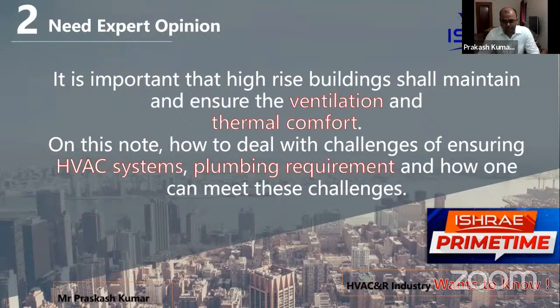Hi everyone. I think this is a wonderful question because piping and ducting are normally one of the most crucial parts of any air conditioning system. In high-rise buildings it becomes paramount because generally these buildings are glass covered, so there's nothing we can do outside the glass cover as it would damage the elevation. Starting with chilled water piping, we generally provide a dedicated shaft from the chilled water plant, located at the ground floor or basement, to each AHU room on each floor. The chilled water shaft should be adjacent to the AHU room, but after erection of the pipe, the common wall between the AHU and shaft should be completely sealed.